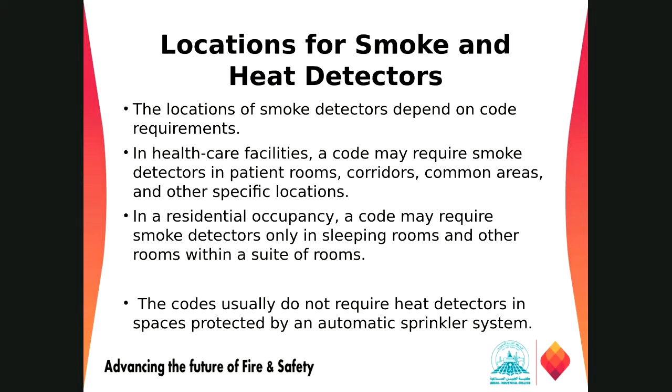Now moving on to the location of heat detectors, right? So the location of the detectors is based on the code requirement. Healthcare occupancies may need a smoke detector in patient rooms, corridors, common areas, and other specific locations. In residential occupancies, a code may require a smoke detector only in sleeping rooms and other within a suite of rooms, right? But in most cases we can see them inside the room in the normal case.